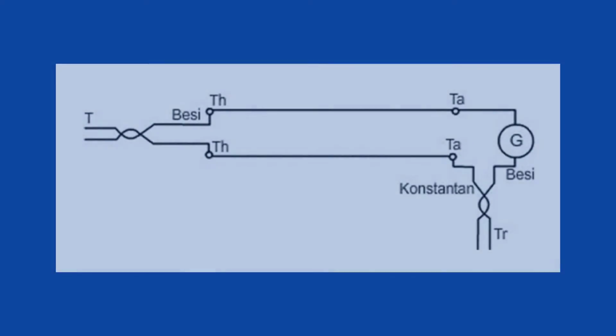It serves as a low and high temperature sensor. Temperatures as low as 300 degrees Fahrenheit to high temperatures used in industrial processes of steel, glass, and ceramics that are over 3,000 degrees Fahrenheit. Thermocouple is formed from two different types of conductors, iron and constantan, wrapped together.